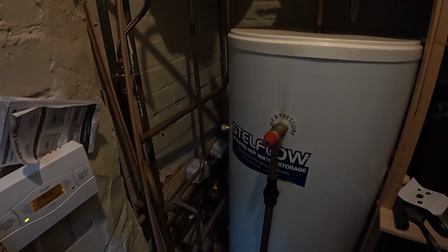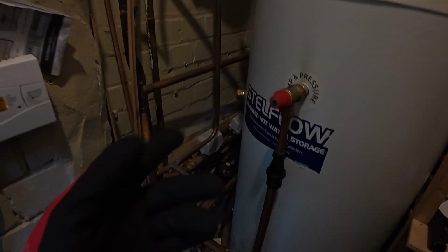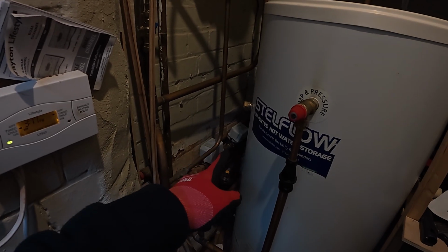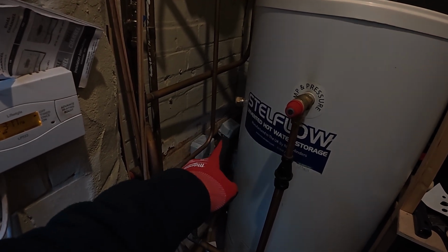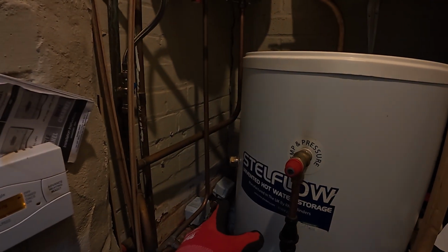One of the jobs for today. This is on an oil boiler, hence why the place smells of oil, but I'm obviously not oil qualified. It's got nothing to do with the boiler because the heating's working. And one of the zone valves, that one back there, is the hot water zone valve, and hot water's on. Cylinder stat is set to 5. Well, I don't know if you can see it, but yeah, set to 5. But that's not opening up.